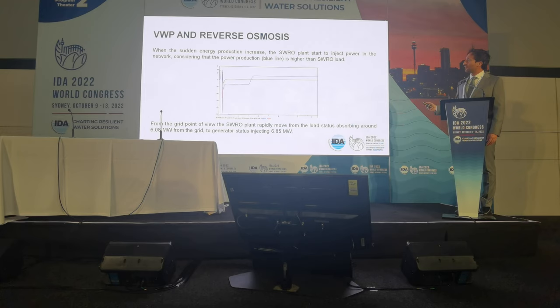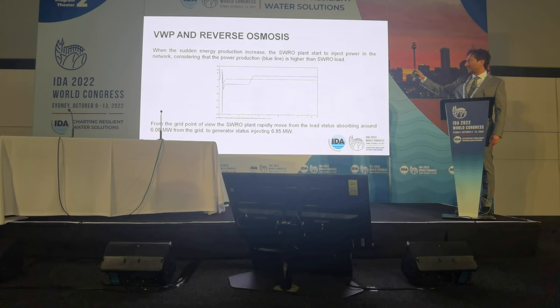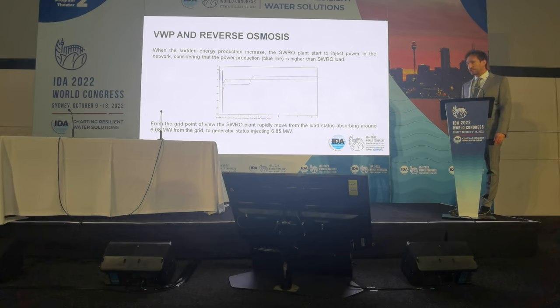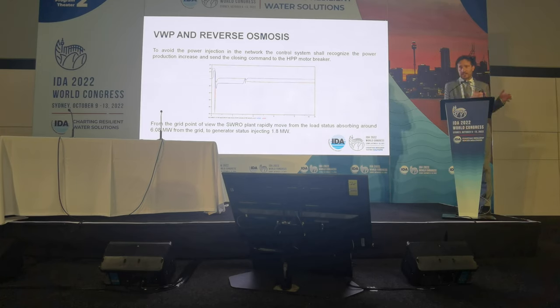If we are using four trains, we pass from consuming around 8 MW to potentially becoming a producer of energy in a very short time. Most of the time we cannot do that because the off-taker will say: I don't want the energy, you have to cut it. But if we are able to start another train, increasing the production in this water RO plant, we can see that we are really controlling the power — the system recognizes the sudden increase of energy and we can react accordingly.